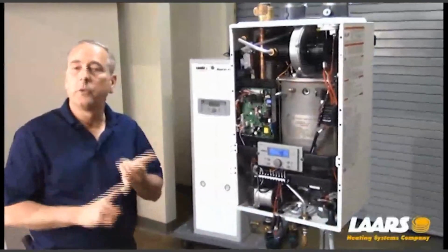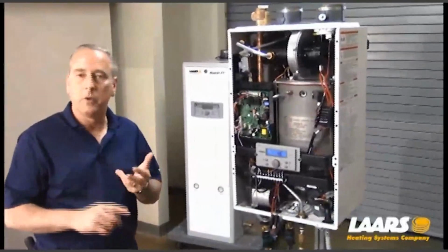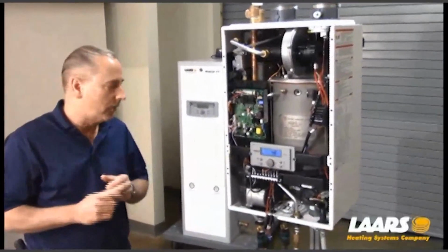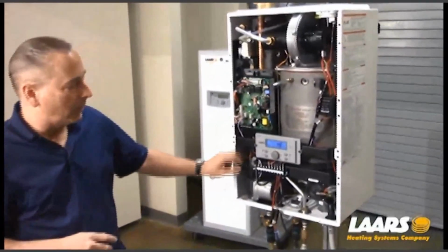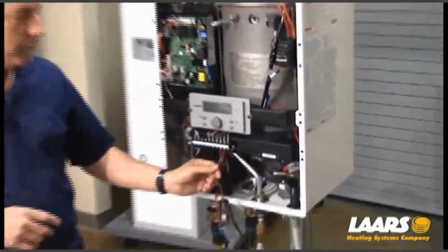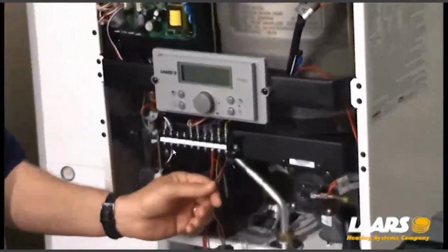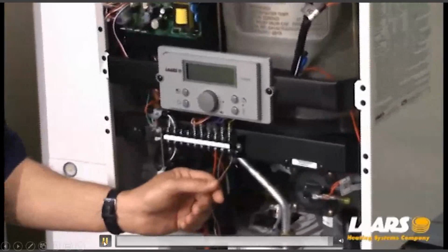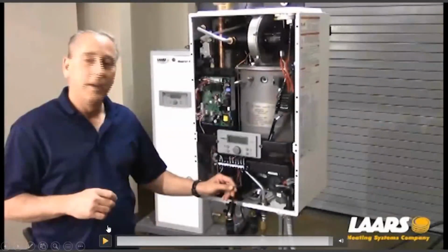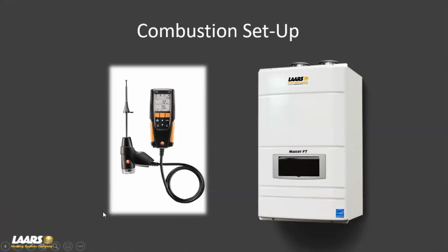Okay, so now that we've got our central heat set point set, the domestic hot water, and an outdoor reset curve, what we're going to do is power off the boiler, reinstall the outdoor sensor, and then you can power the boiler back up and operate the boiler. So with that, I'm going to move forward to the next section. So that's the programming. And again, we have videos online. We also have startup guides, and all of this information is also in the installation and operation manuals.